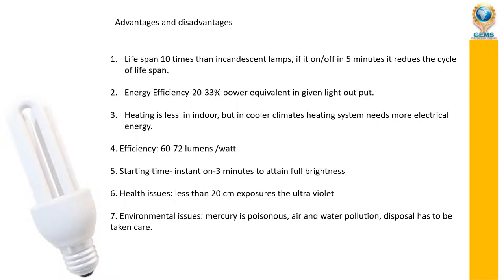The lifespan of a CFL is 10 times more than an incandescent lamp, but if you switch it on and off within five minutes repeatedly, it will reduce the lifespan. The energy efficiency is 20 to 33 percent equivalent in power for a given light output — meaning the same light output is available using only 20 to 33 percent of the power.